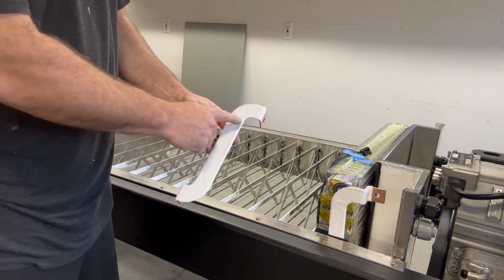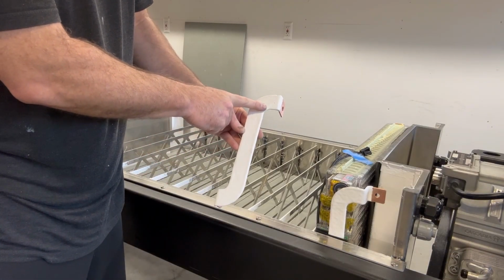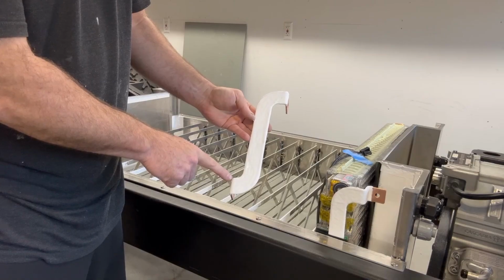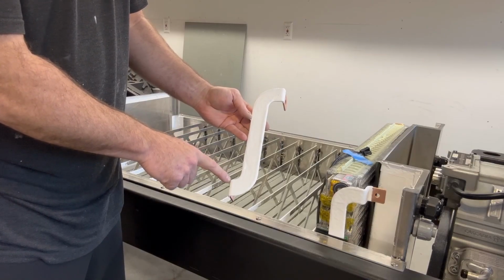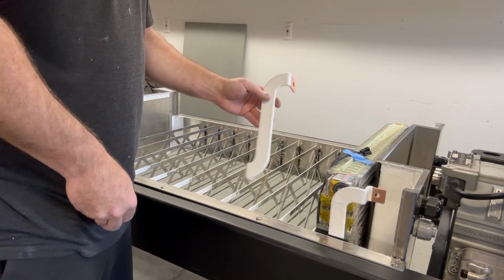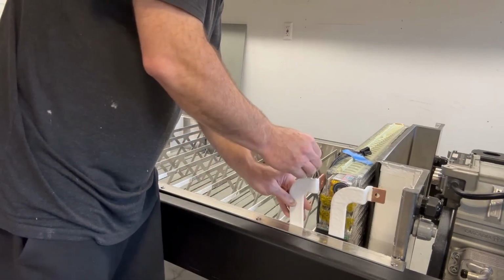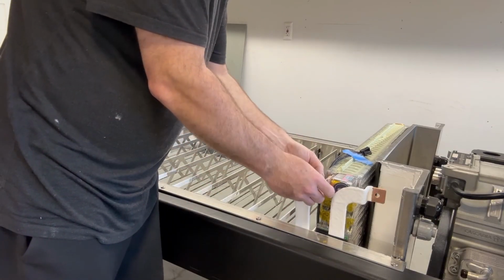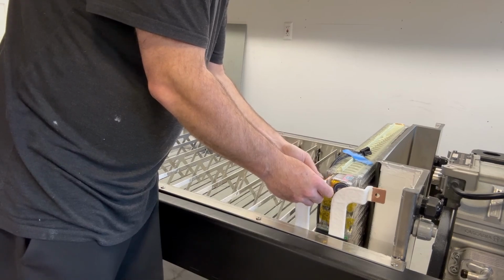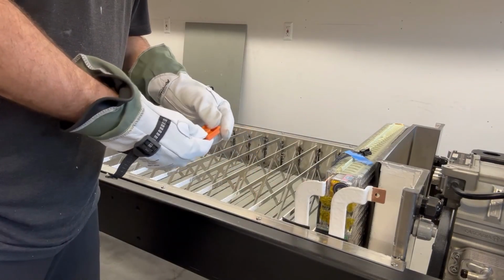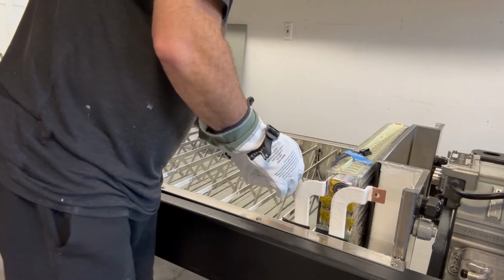Note that the bus bar has a top and bottom. The top has the longer leg and the bottom has the shorter leg. This is necessary in order to keep the bus bars a healthy distance away from the trusses. For each subsequent module, I am loosely installing the next bus bar onto the module that is installed. Now we will place the orange insulating cap over the bottom connection of the module.